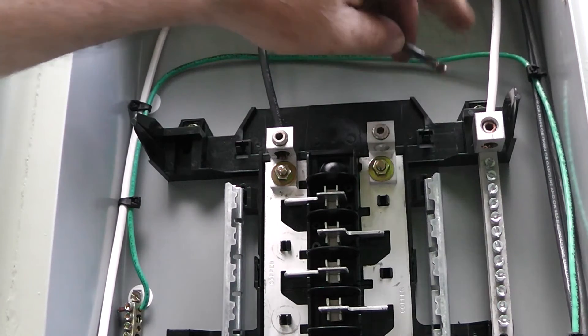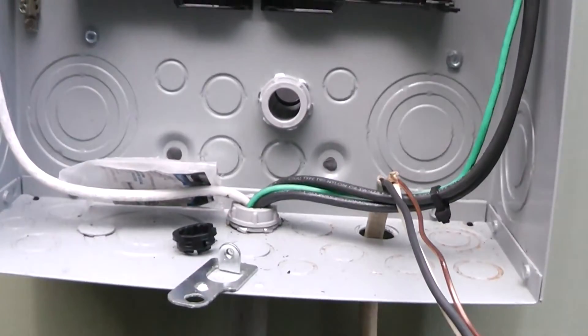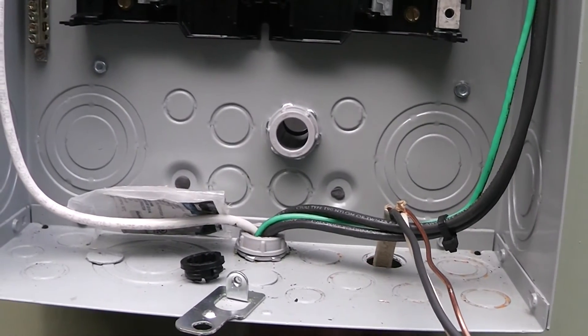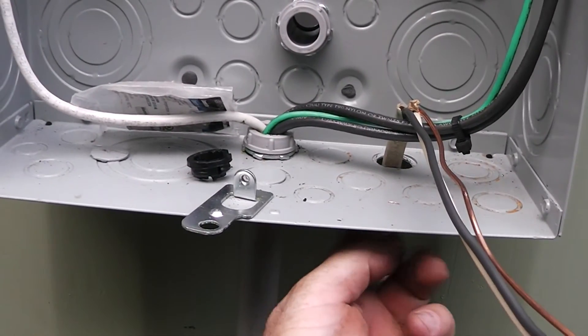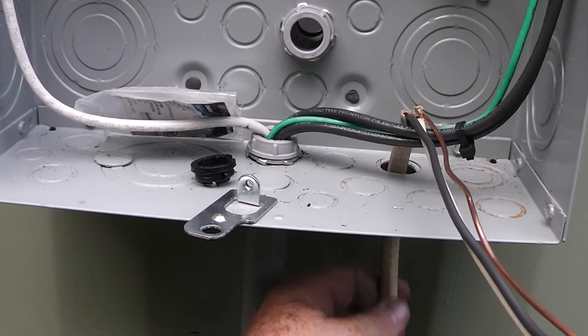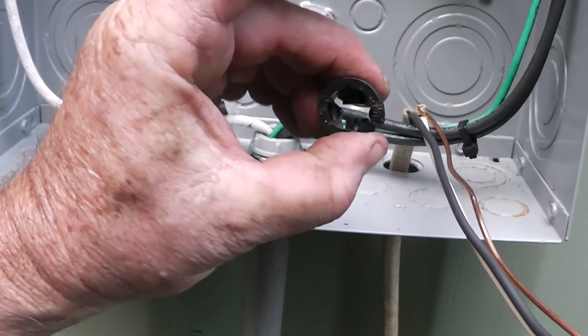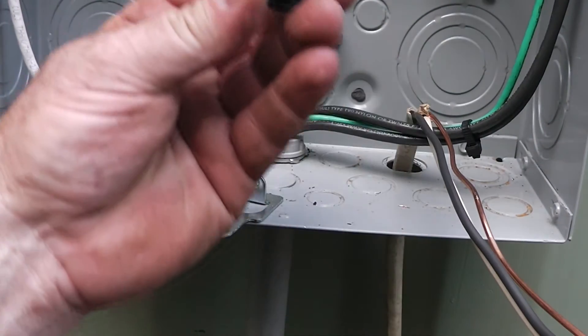But like I said, this was just for demonstration purposes only. Also, I noticed you got some wires like this in your panel. This is just a piece of Romex, I'm getting ready to run the ground yet. This is an old piece of 10-2 and it's white, that's how old it is. They make these things, they're insulators called hitlocks. They sell them at Home Depot and supply houses.